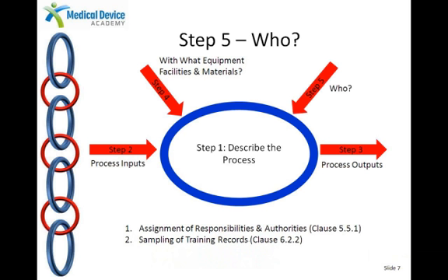The next step is who is going to be doing this inspection. So how do you decide who's going to be doing inspection? How are they assigned? Which people are qualified to do what types of product? If you have an optical product, you might not have all your inspectors qualified to do optical inspection. Maybe only some of them can. Maybe you have printed circuit boards. Maybe only some of them are qualified to inspect solder joints. You also want to look for training records. So you might have a follow-up trail identifying the names and the titles, and you're going to look for specific training on whatever procedures they were performing.